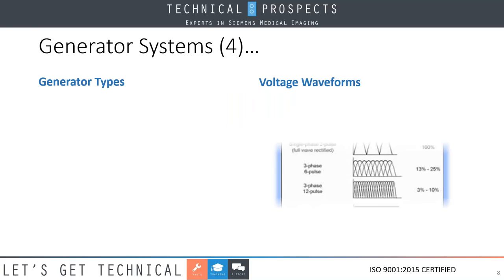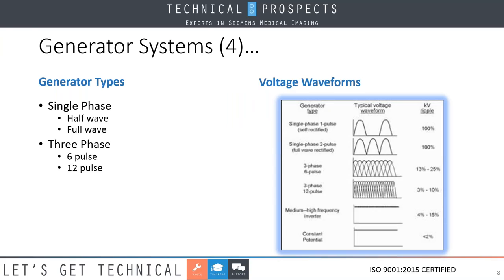So moving on from here, let's take a look at some of our voltage waveforms and the types of generators that we have. If you notice here, you've got single phase, half wave, and full wave generators. A half wave generator was typically found in old dental units where the X-ray tube was strictly the rectifier itself. When we use a full wave system, we add a diode into the secondary, which then will invert the other pulse, giving us a full wave rectification, as you can see from the different waveforms.